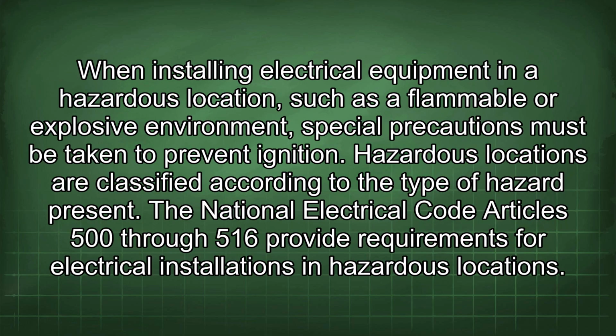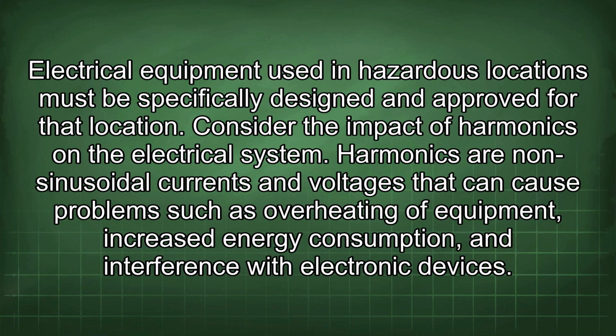When installing electrical equipment in a hazardous location, such as a flammable or explosive environment, special precautions must be taken to prevent ignition. Hazardous locations are classified according to the type of hazard present. The National Electrical Code Articles 500 through 516 provide requirements for electrical installations in hazardous locations. Electrical equipment used in hazardous locations must be specifically designed and approved for the location.